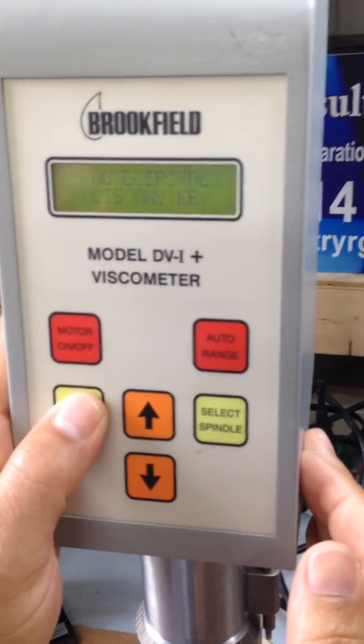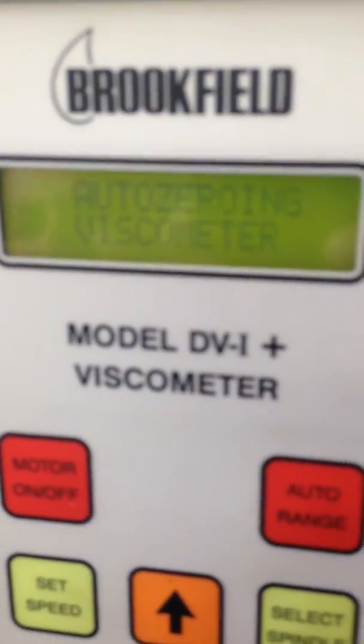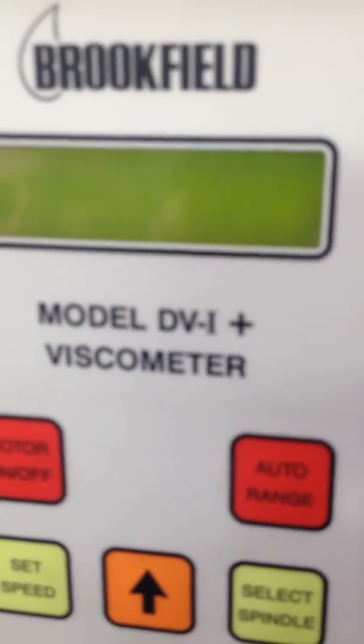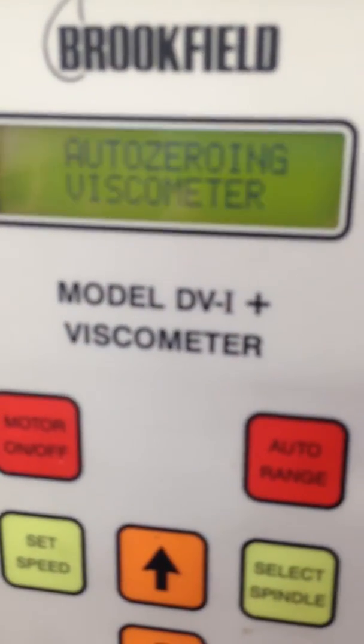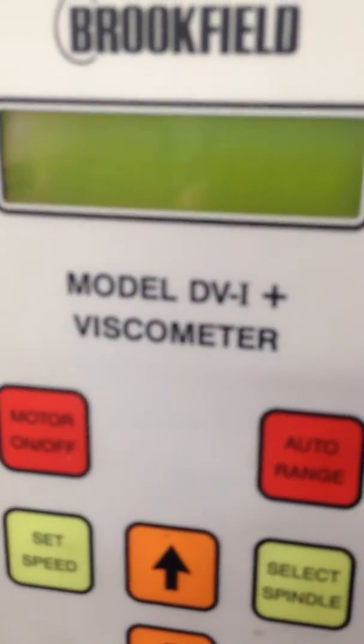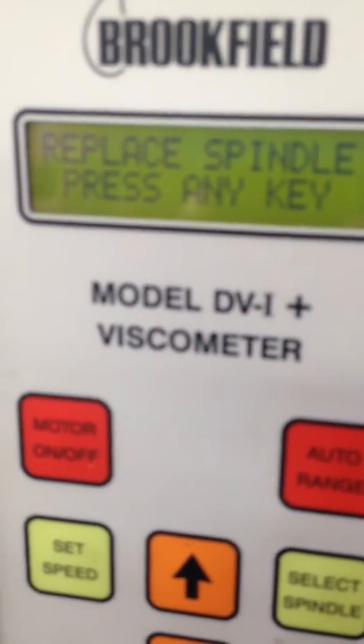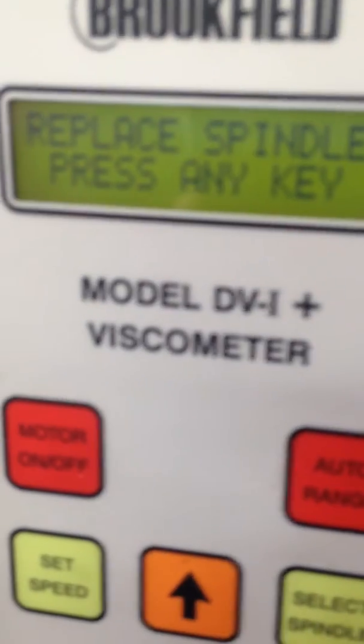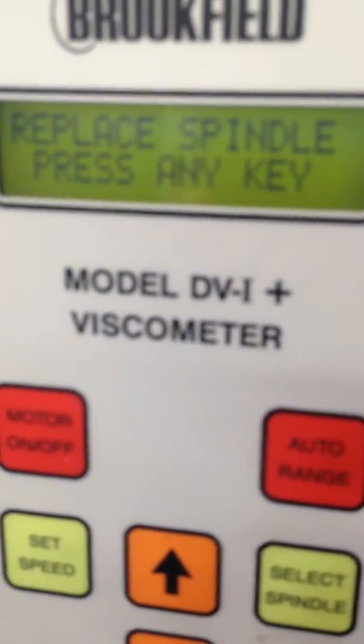Remove spindle, press any key. So right now there's no spindle at the bottom. Press any key and what it's going to do for you is auto zero. It's actually turning on the bottom with no spindle, doing auto zero for you. Once the auto zero is done it's asking you to put the spindle.